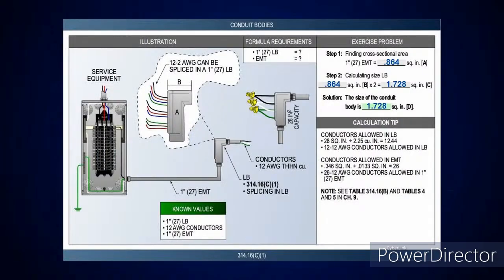For the first one we started last week, we were looking at conduit fill — or conduit body fill. One of the things we were trying to talk about is the size of the conduit body and what you would need in it to make splices. As Bill stated last week, he found one. These conduits tell you how much square inches are in them. If you go over and look at NEC 314.16 C1, that's where you're going to pick up this information.